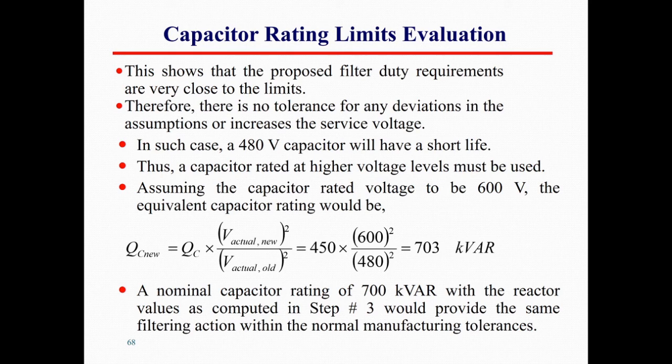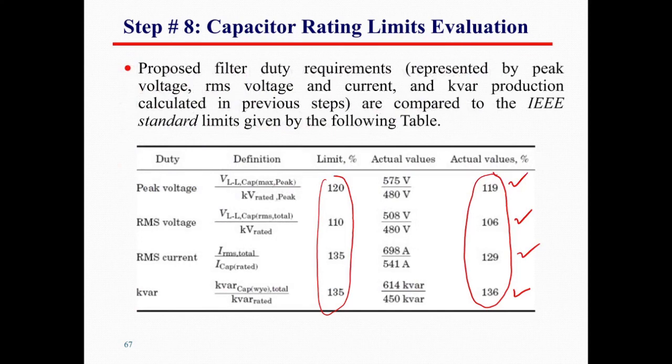Okay. This slide shows that the proposed filter duty requirements are very close to the limit. So as we said, there is no tolerance for any deviation in the assumption or increase in the source voltage. In such a case, the capacitor will have a short life, right? Because, again, there is no tolerance. The value is very close to the standard, right?